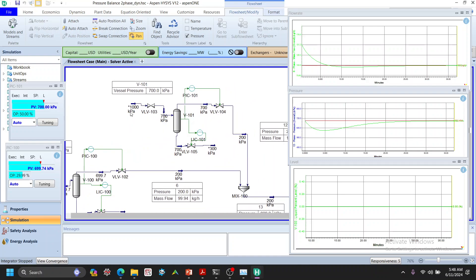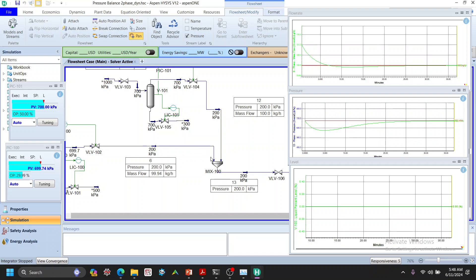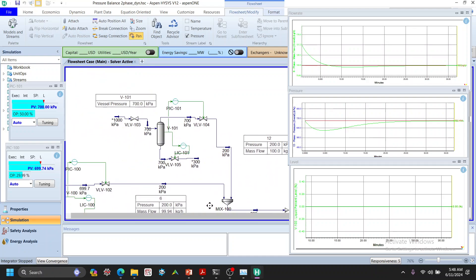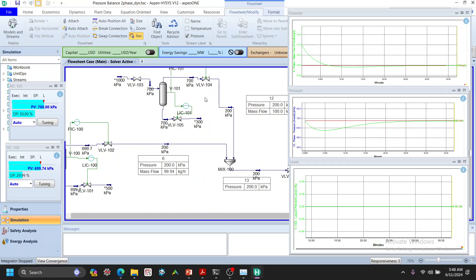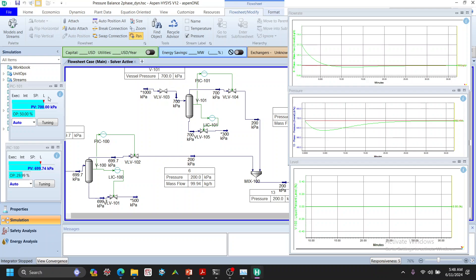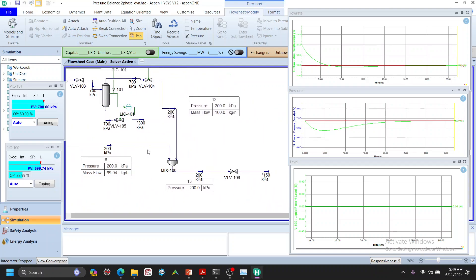There's also another air source at 1000 kPa, and these are mixed through the pipeline with an outlet pressure fixed at 150 kPa. The pressure controller for vessel 101 (PC 101) is set to 700 kPa with a valve opening of 50%, and PC 100 for the other vessel also has a set pressure of 700 kPa with a valve opening of 30%.